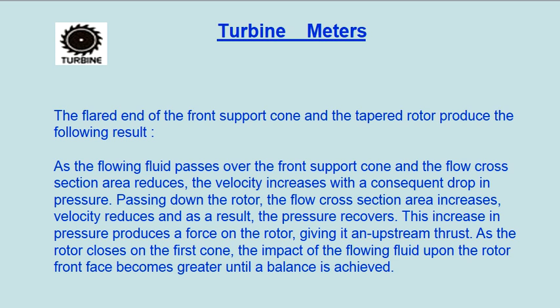Passing down the rotor, the flow cross section area increases, velocity reduces and, as a result, the pressure recovers. This increase in pressure produces a force on the rotor, giving it an upstream thrust. As the rotor closes on the front cone, the impact of the flowing fluid upon the rotor front face becomes greater until a balance is achieved.